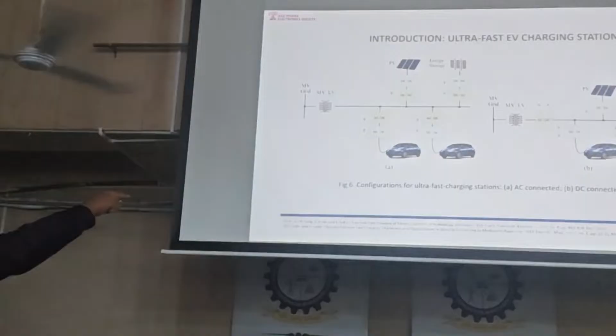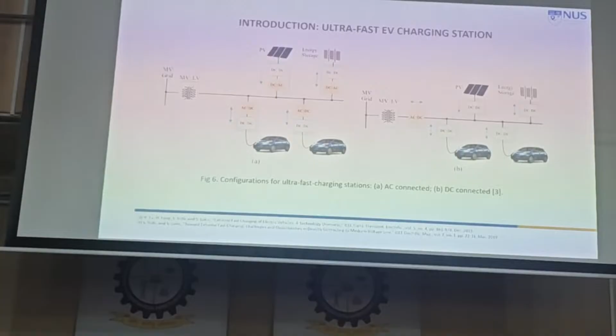If you go for the first scheme, MV AC to LV AC, that is the AC line, you integrate PV, DC to DC converter, DC to AC converter, then integrate it there. To charge, the AC is converted to DC, then DC to DC converter, then fit into the charger, if it is AC connected. If it is DC connected, I replace the AC-DC, DC-AC converters into one box, AC to DC converter in the front end. Then I can interface PV through a DC to DC to the DC bus, and from the DC bus, a DC to DC converter to charge the car and the energy storage system. That's a comparison between the two.